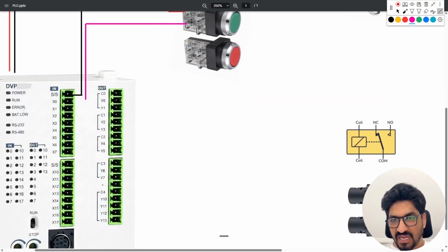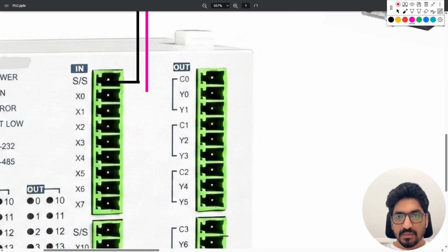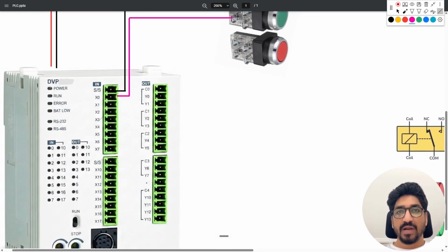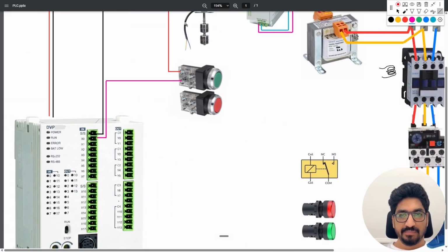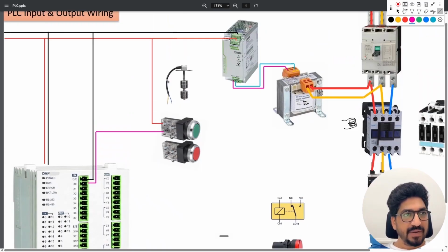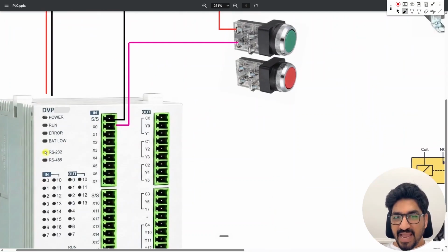Now I can connect to any port as per the programming. So if I connect this one, it becomes X0, right? So as per my program, X0 is connected to the start button. So what happens when I press the start button? Current which was waiting here will go and sink here, and it comes out of this negative and goes to the negative source. Circuit is complete, my X0 is triggered. That's what happens when I press the green button.